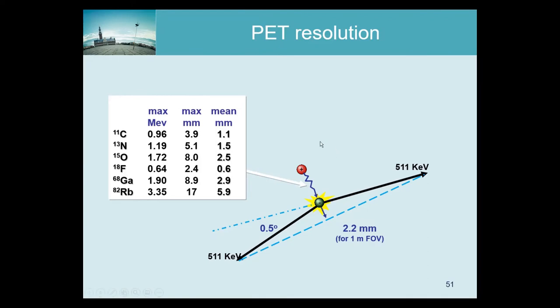Resolution effects are a bit different in PET than in SPECT. In SPECT, a photon is emitted from the isotope and travels in a straight line. That is not the case in PET: a positron is emitted with a lot of kinetic energy and must travel and interact with many electrons before it can annihilate. In all these interactions it loses energy, and only when its energy is nearly zero can it interact with an electron and annihilate to produce two photons. This travel distance causes a loss of resolution.